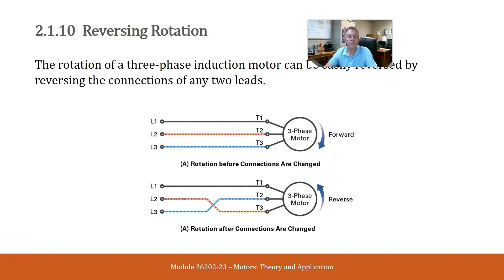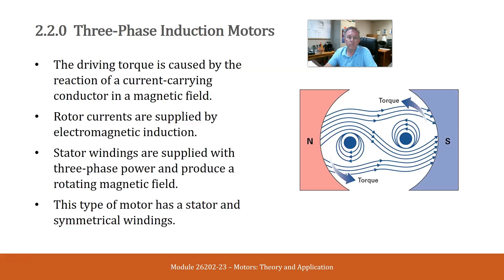Reversing rotation. The rotation of a three-phase induction motor can be easily reversed by reversing the connection of any two leads. The driving torque is caused by the reaction of a current carrying conductor in a magnetic field. Rotor currents are supplied by electromagnetic induction. Stator windings are supplied with three-phase power and produce a rotating magnetic field. This type of motor has a stator and a symmetrical winding.